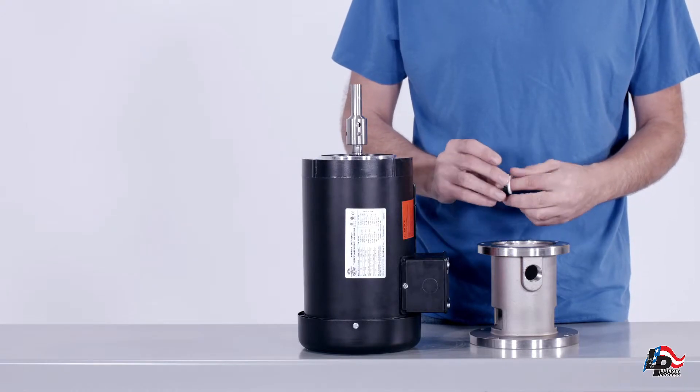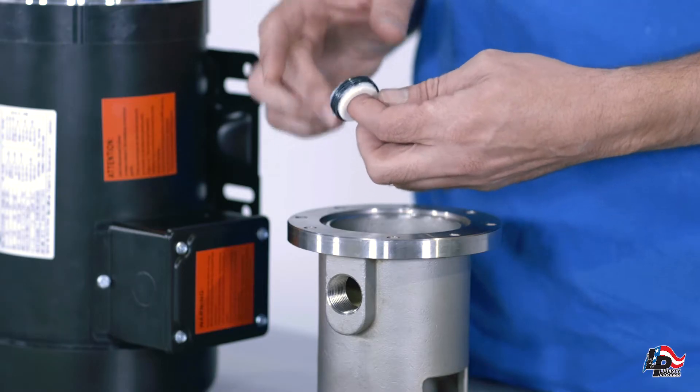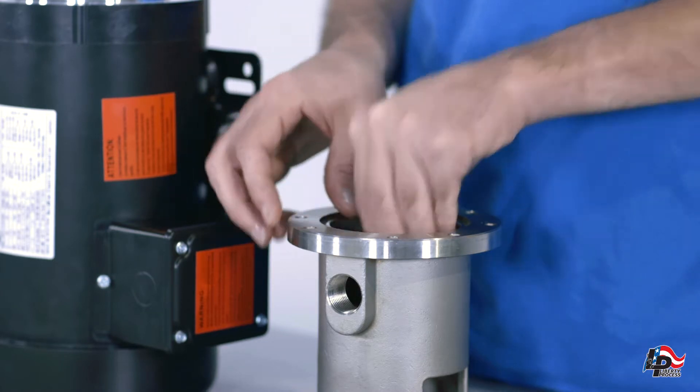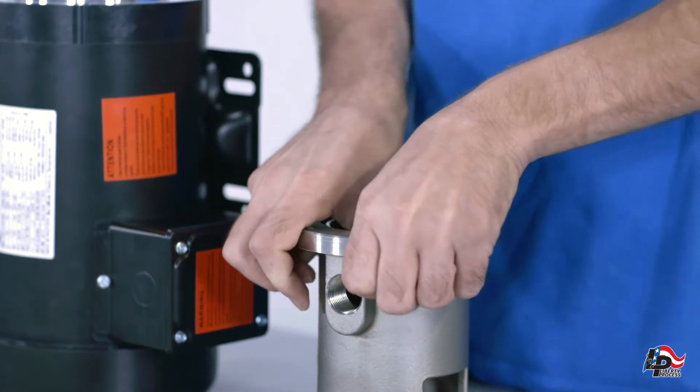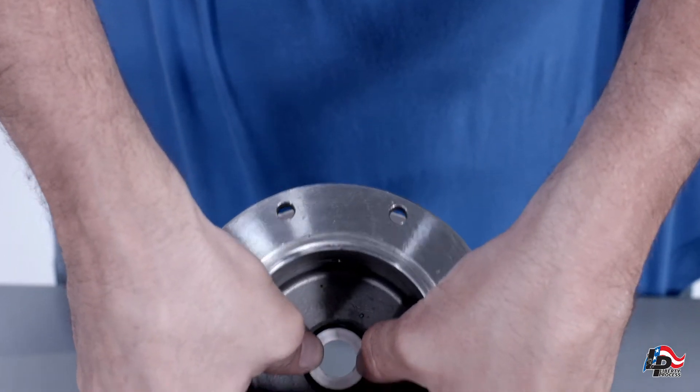Lubricate the outer diameter of the seal stationary face with liquid soap. Using your thumbs, gently press the stationary face of the mechanical seal assembly into the discharge casing until it seats.